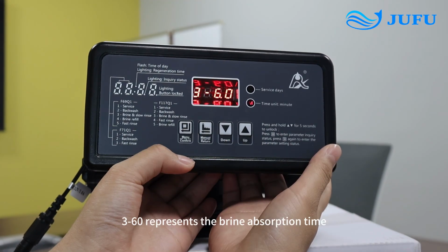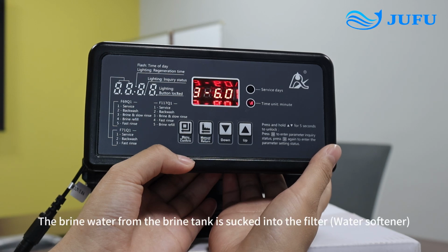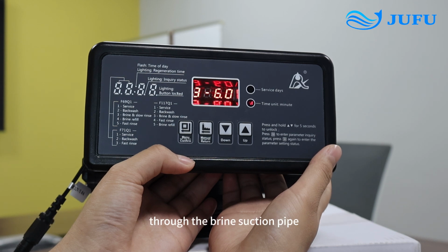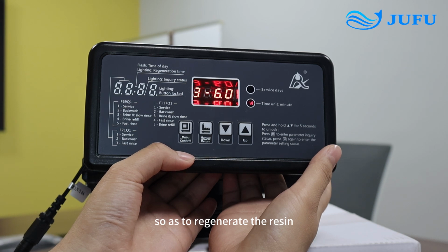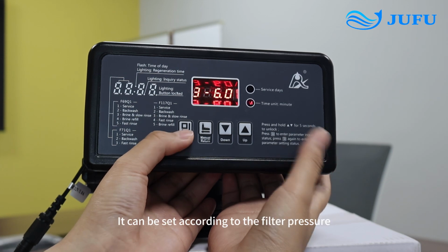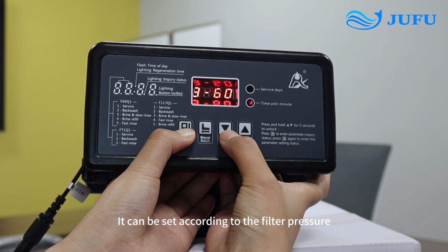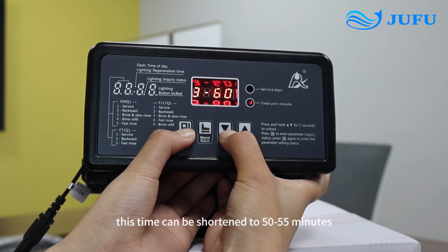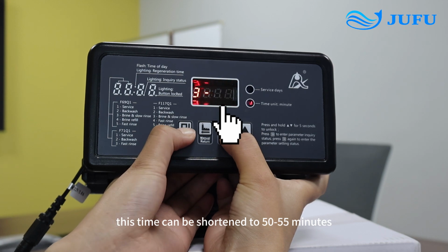360 represents the brine absorption time. The brine water from the brine tank is sucked into the filter through the brine suction pipe, so as to regenerate the resin. This time is now set to 60 minutes. It can be set according to the filter pressure. If the pressure is high, this time can be shortened to 50 to 55 minutes.